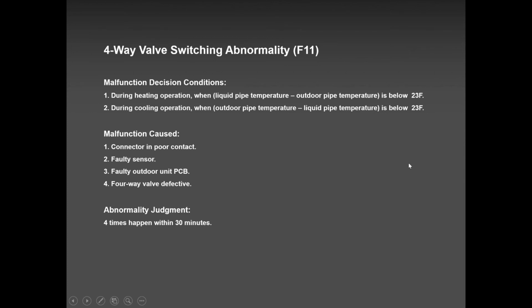And if it is a system that has been running off and on and it's getting F11, chances are maybe, I don't know, you are low on gas, or a defective four-way valve coil, or the four-way valve itself. And to change the four-way valve, it's not fun, because many of my guys, when they change that valve, not the coil, guys, not the coil, the valve, they forget to put a cold, wet cloth while they are brazing. And guess what? With the Teflon inside, the material inside is something very close to plastic. It melts, and we have the same problem.